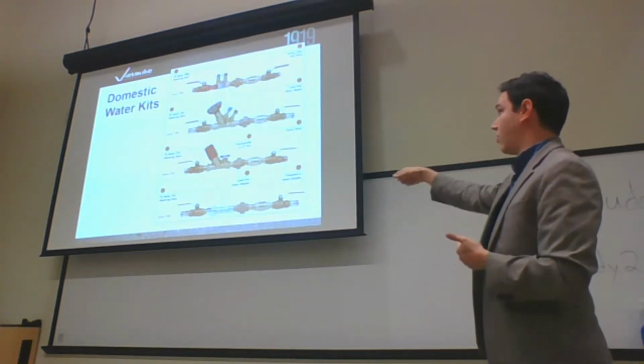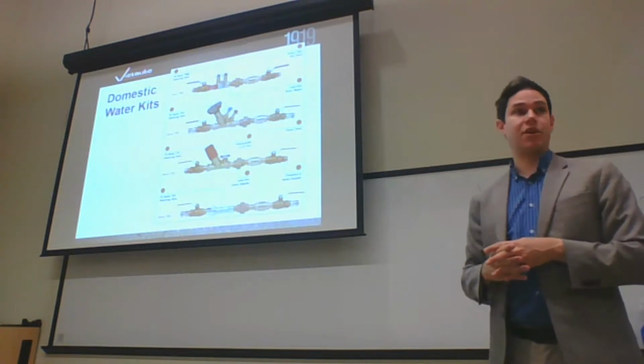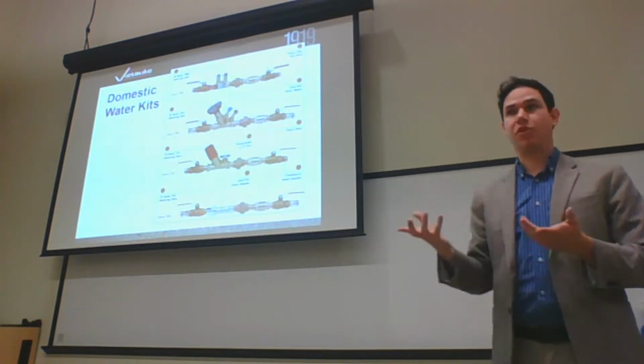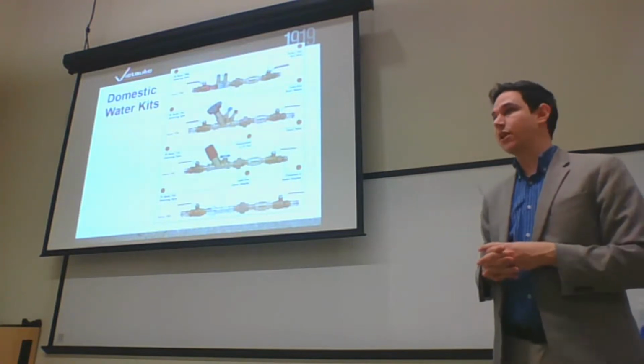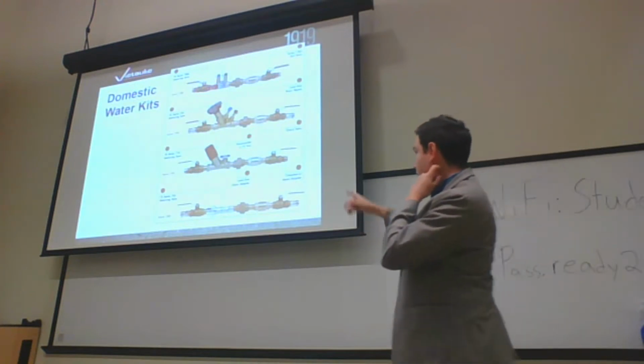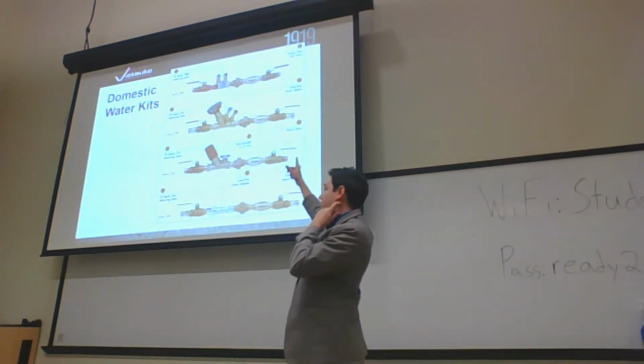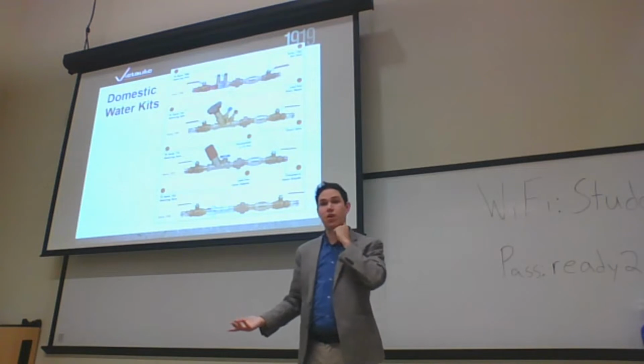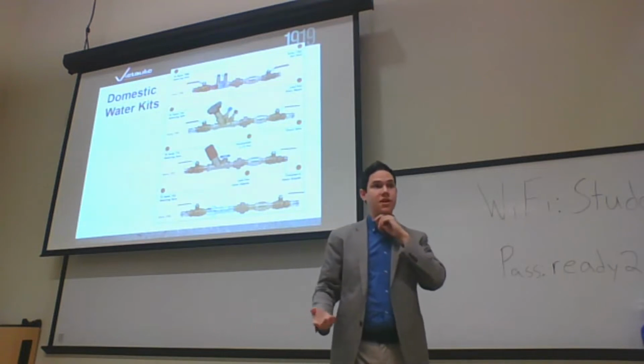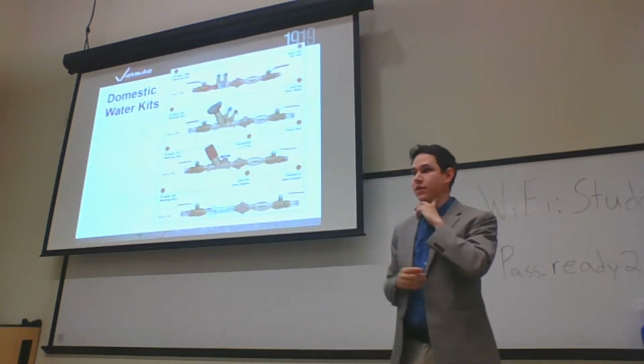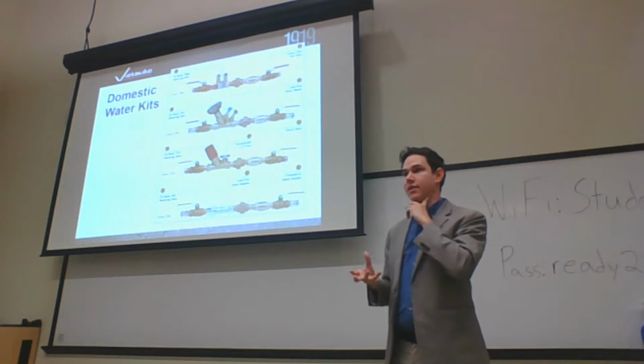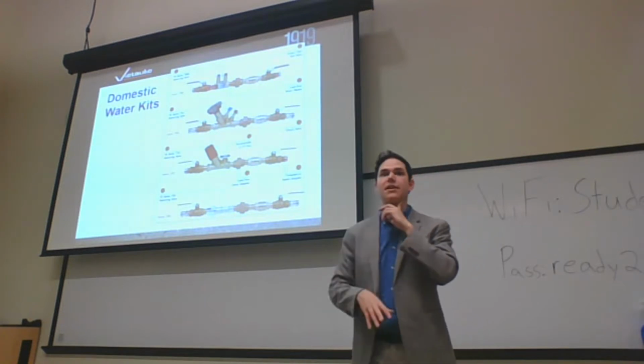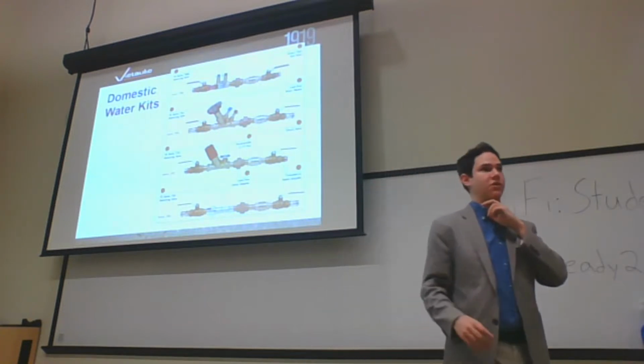And of course, all this is recirc lines, so it's normally 1/2 and 3/4 inch. The globe style, the first or the second option, could also be installed on branches or risers if you want to balance the whole supply, not the recirc line, but the supply side. It could also be installed on that.